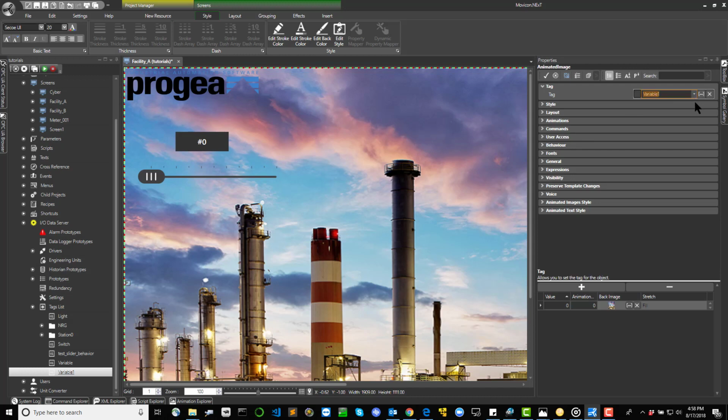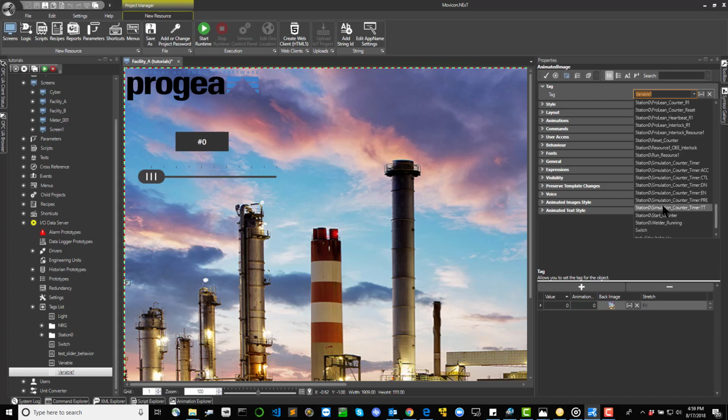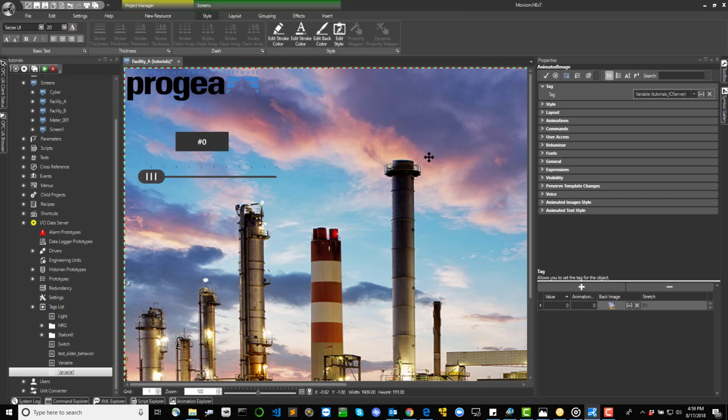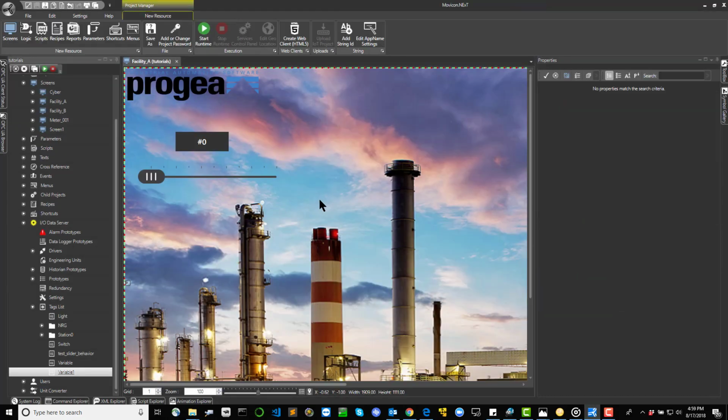It is also possible to select the OPC UA browser tab from the tag browser window. Through it, to access the list of OPC UA servers available, the window can be used for selecting the tag desired, confirming with an OK to assign to the object. This operation will only work for the project server when it's launched beforehand.